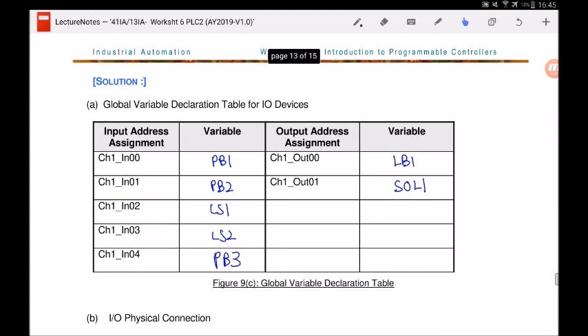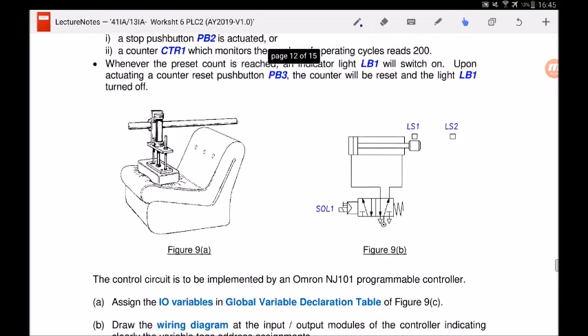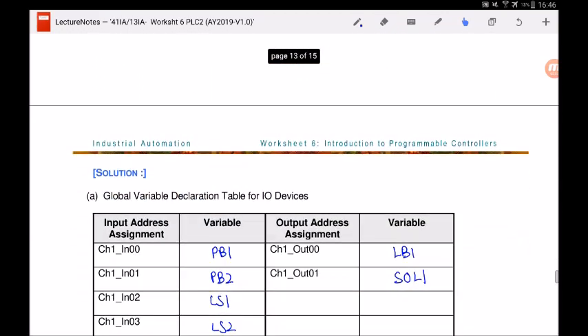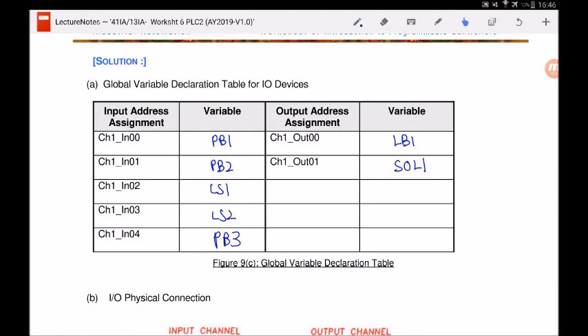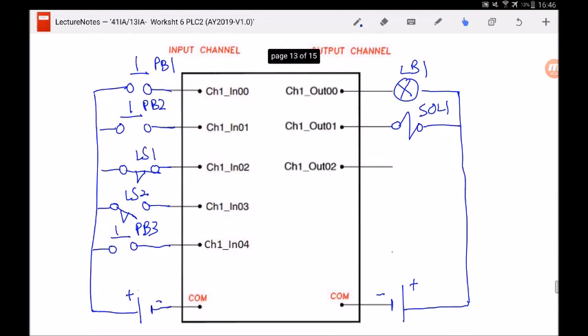Note that counters and timers are not declared in the global variable declaration IO table because they are software functions within the PLC, not physical input/output devices. Only physical elements — push buttons, limit switches, light bulbs, and solenoids connected to the input/output cards — are declared in that table. We will now design the PLC program in ladder to achieve this operating sequence.